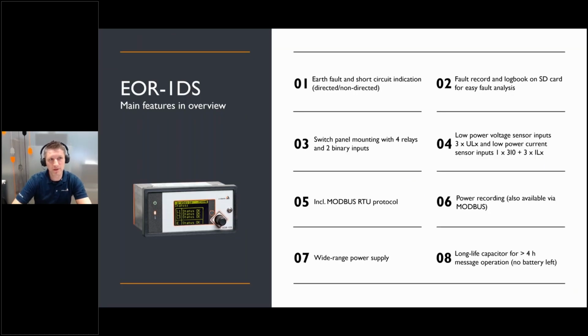Here a short overview of the main features of the EOR-1DS. So we have earth fault and short circuit indication, directed and non-directed. As explained, this depends on whether you only measure the current or you measure the current and the voltage in addition. We have fault records and logbooks on the SD card for easy fault analysis. We have 4 relays and 2 binary inputs on board. We have the opportunity to also connect high accuracy low power voltage and current sensors to the device. We have the Modbus RTU protocol on board, and power recordings, especially in connection with low power sensors. This is useful. Then we have a wide range power supply, so you can supply the device with AC or DC up to 260 volts. And we have an internal long life capacitor for an indication for more than 4 hours.